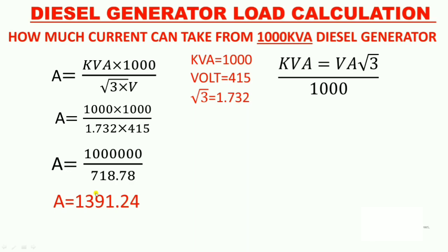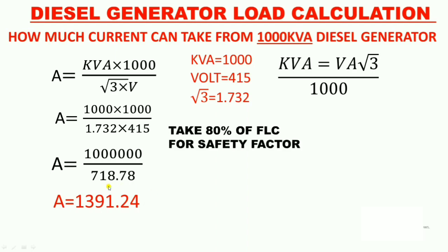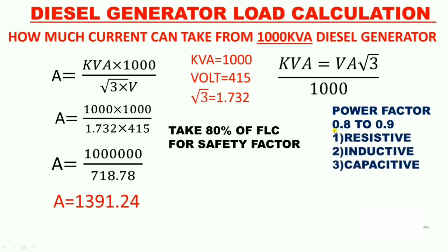1391 ampere is the full load current (FLC), but we cannot take 100% load of any electrical component due to the safety factor and other factors. Also, the diesel generator alternator is designed for 0.8 power factor, and we do not know which type of load will be connected — resistive, inductive, or capacitive. So we take 80% of the full load current as the safe working current.